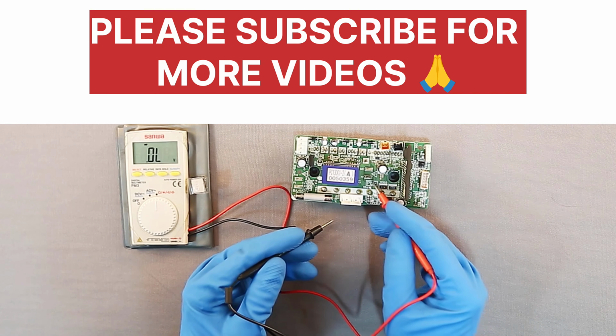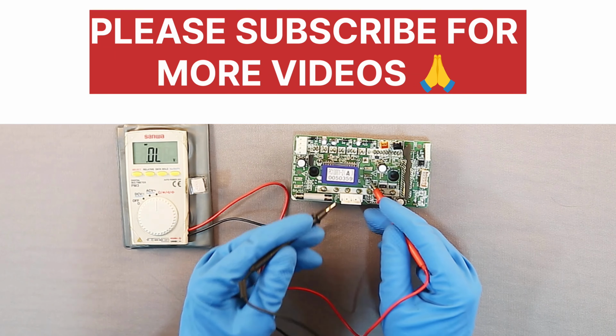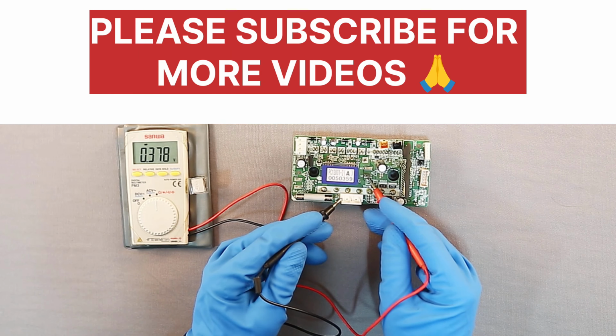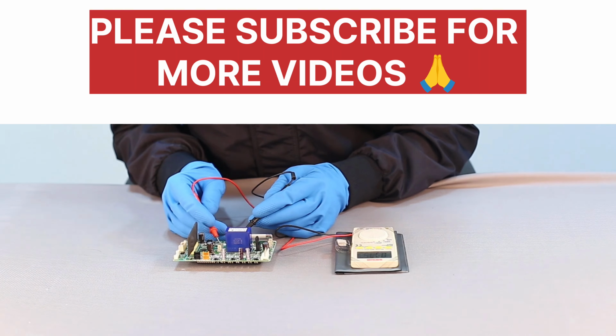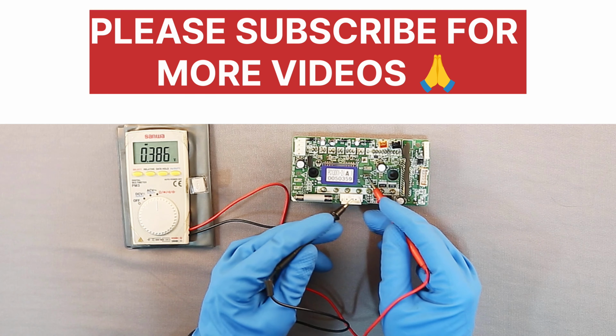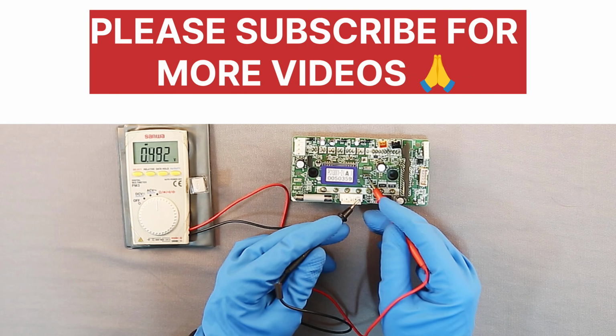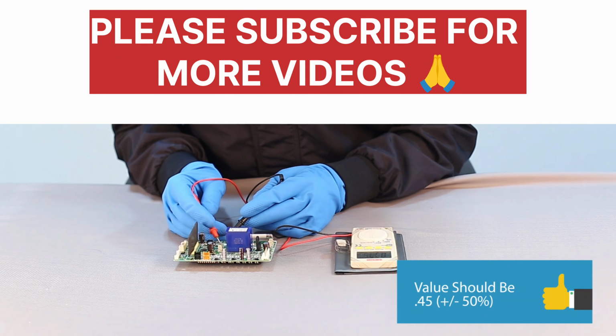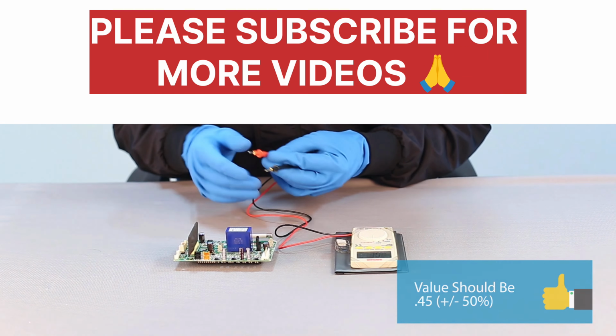Now, put the red probe of the multimeter on N1/N11 and the black probe on point number 1. Similarly, repeat the test between N1/N11 and 2, and N1/N11 and 3. The value should be 0.45 plus minus 50%.